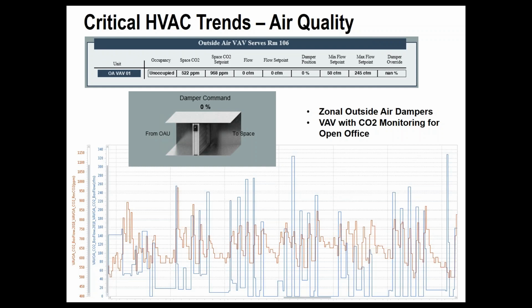So this is air quality. We actually only have one CO2 sensor in the whole facility. We have a nice HVAC system here where we have the ventilation decoupled from the heating and cooling. So our dedicated outside air system generally provides constant volume of outside air to zones, except for one zone where we use demand control ventilation.